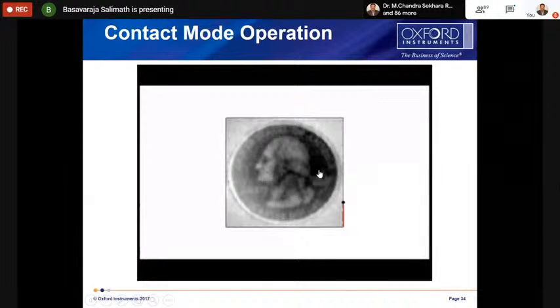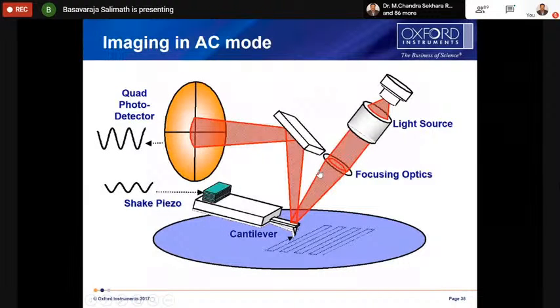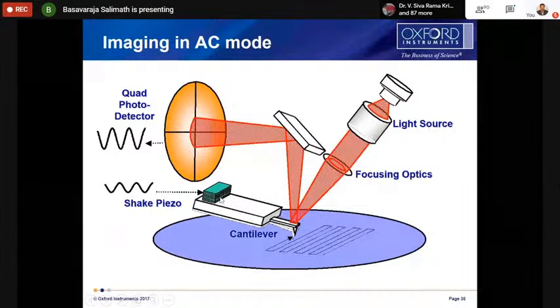In the case of AC mode, it's called tapping mode or semi-contact mode. In this case, there is a small shake piezo, and we apply a little bit of bias to this piezo, then it will start oscillating. This is attached to the cantilever, so the cantilever will also start oscillating. So the tip is oscillating and lightly tapping the surface.